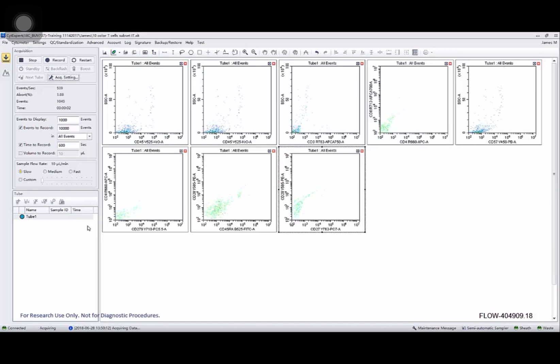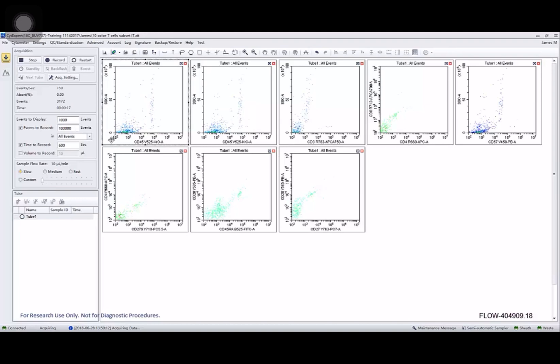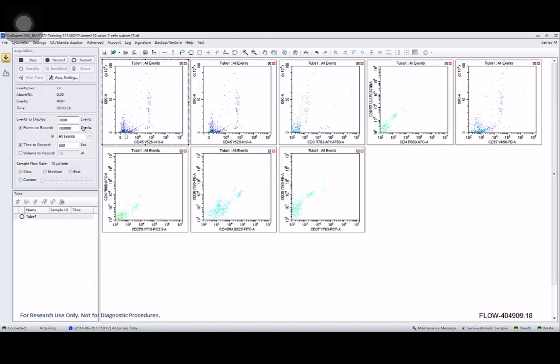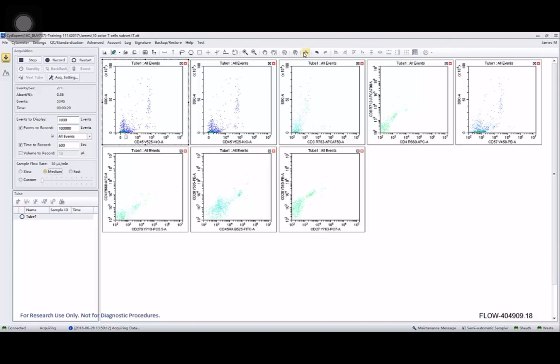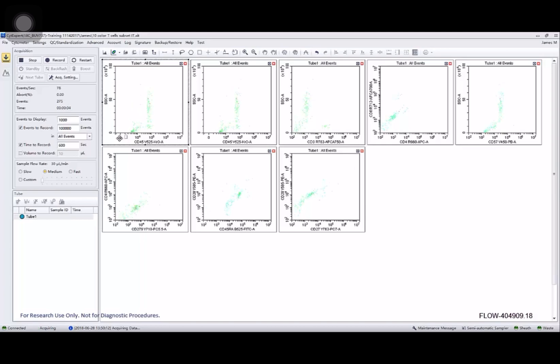And now I'm going to begin collecting a little data. This is lysed Beckman Coulter Immunitrol, a whole blood control product. I can change how many events I'd like to record when I begin recording. Play with the lin log display slider until I get populations appearing the way I like. Change the speed of my pump. I'm going to use a manual threshold here on CD45 in the Krome Orange channel to get rid of any debris that's not CD45 positive, so not our blood leukocyte populations.